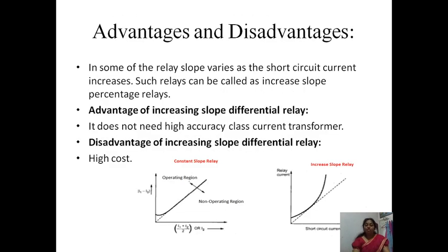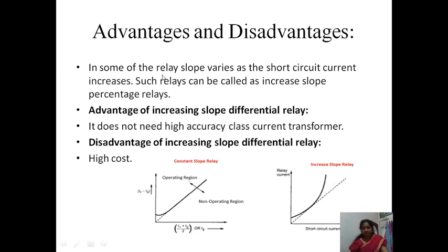Advantages and disadvantages of constant slope relay versus increased slope relay: in some relays, the slope varies as the short circuit current increases — such relays are called increasing slope percentage differential relays. The advantage of an increasing slope relay is that it does not need high-accuracy class current transformers. The disadvantage is its high cost. We are generally using constant slope relays.